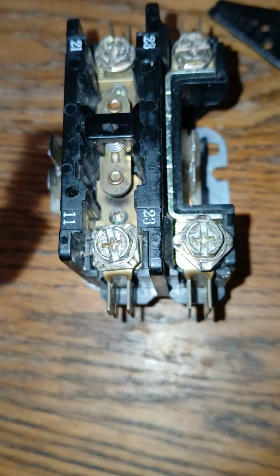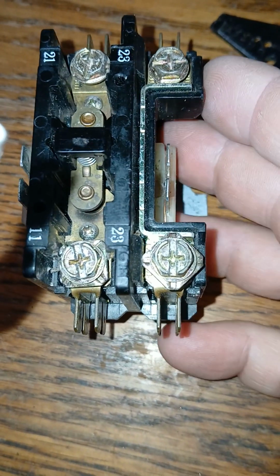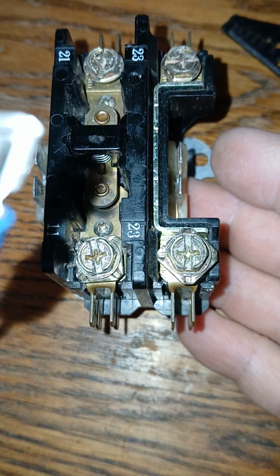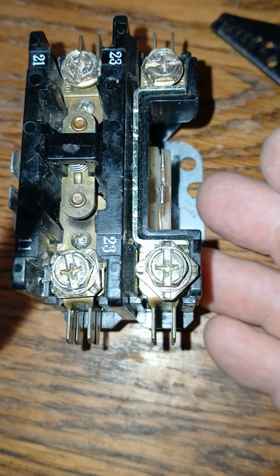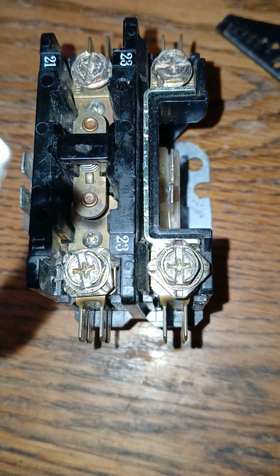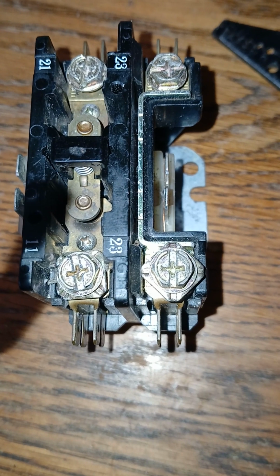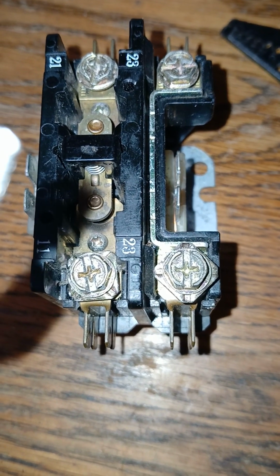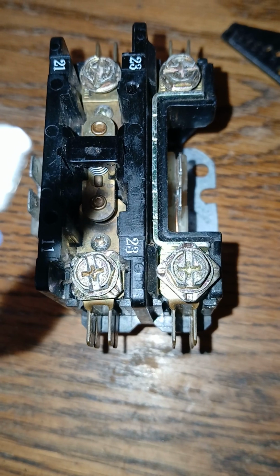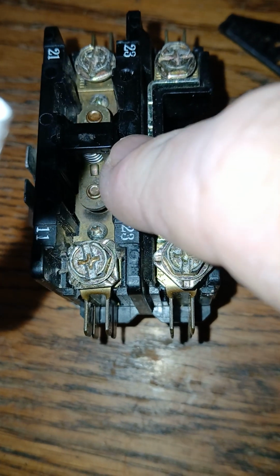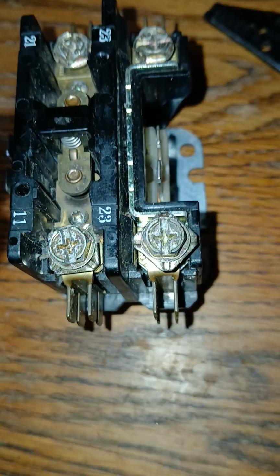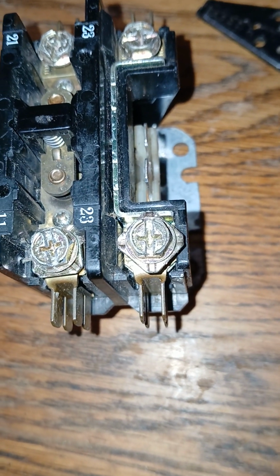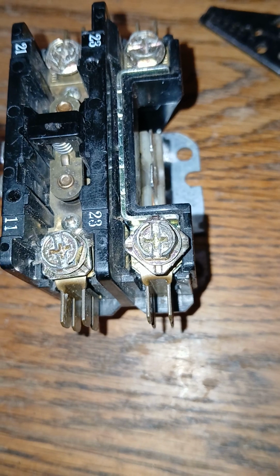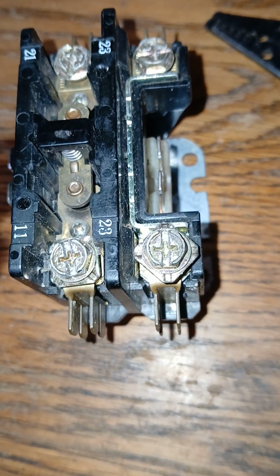So the question being, number one, what is the contactor for? Think of it like an off and on switch. It powers up the condenser outside. It powers the compressor and it powers the condenser fan motor. So if it's energized here, if this is pulled in by the low voltage and the high voltage goes here, high voltage goes here, now we have high voltage. But once a certain criterion is met, then the system would cut it off.